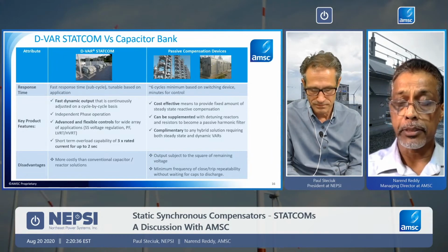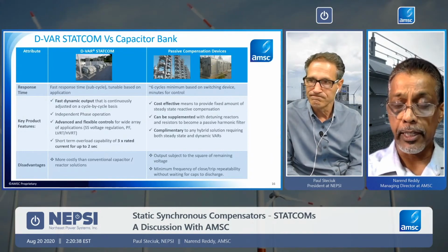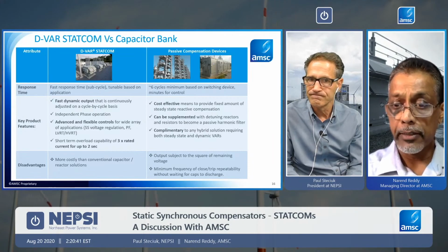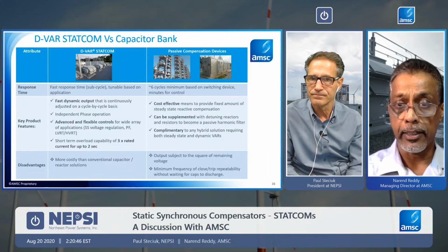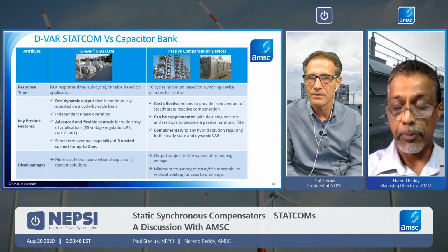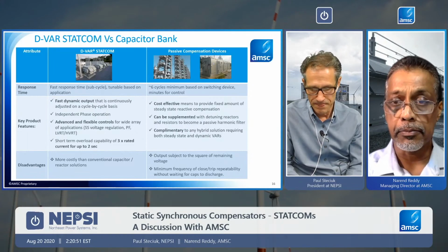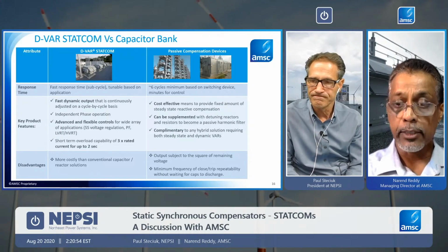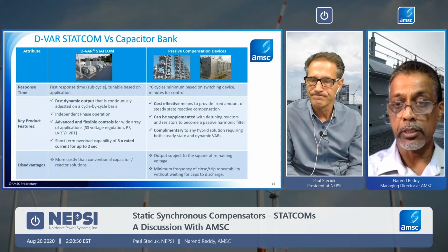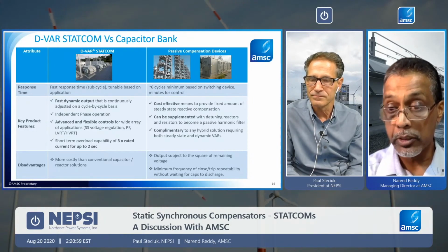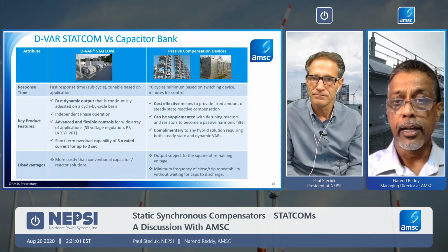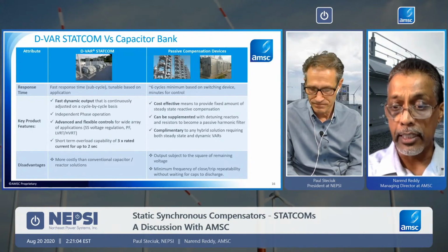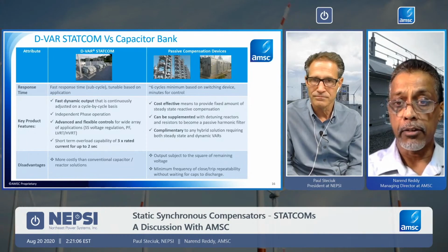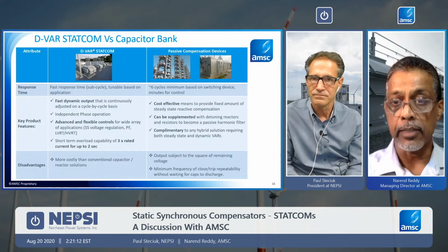As opposed to a passive compensation device, a cap bank or a reactor bank, both of them do provide reactive power. Reactors provide the inductive or lagging reactive power. Capacitors provide the leading reactive power. But they are switched. They are in chunks. They're switched using conventional switching devices, cap switches and all that, which typically take 6 cycles to be brought in. And then, of course, minutes. If you're doing control of these devices, it takes minutes in terms of changing power factor and all that.